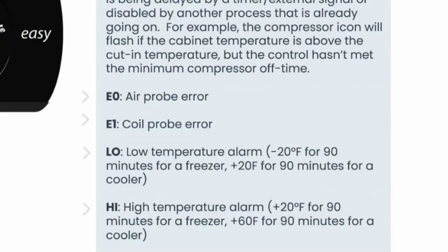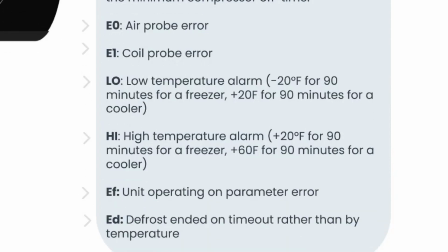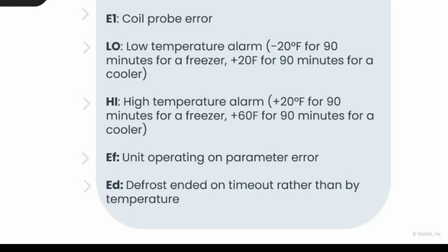So since it comes with that harness, the low and high temperature alarms, you can see the different thresholds for those as far as when it'll kick off the alarms. EF means the unit's operating on a parameter error. ED means that the defrost ended on time rather than temperature. So that doesn't necessarily mean that there's a problem with the unit if you have that ED show up on the display. It just means that usually under normal operation, that unit's going to terminate defrost on temperature rather than time. So if it goes the entire time duration on that, there could potentially be an issue, could be the beginnings of maybe a frozen up evaporator coil, which would maybe require a little bit more troubleshooting on that end of it.